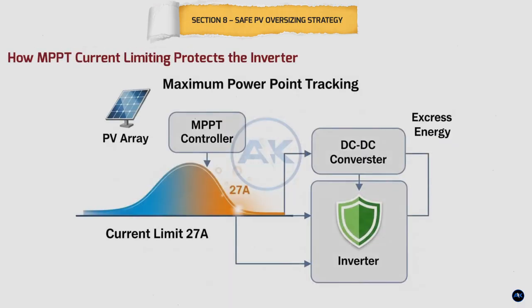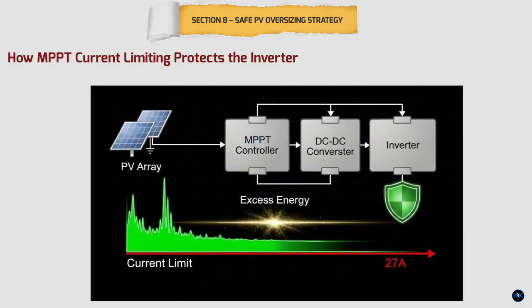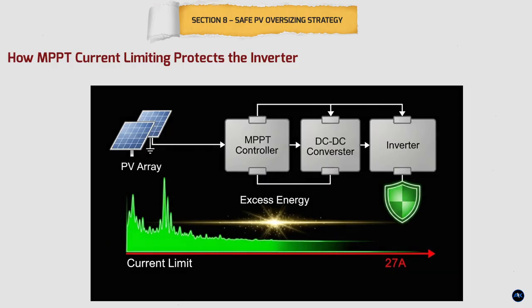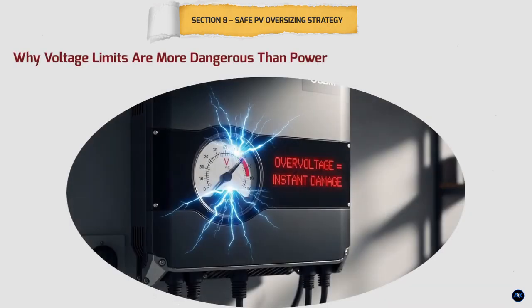How MPPT current limiting protects the inverter. Modern hybrid inverters protect themselves using MPPT current limiting. When the solar array can produce more power than the inverter can accept, the MPPT simply limits the current. The extra power is not used and nothing gets damaged. But here's the critical warning. Voltage is different. If you exceed the inverter's maximum PV voltage even for a moment, there is no limiting, no protection, and no second chance.